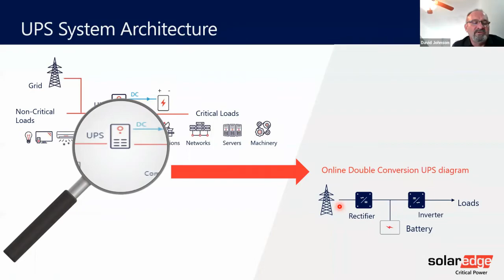So, limitations of a traditional monolithic system. We take a look at the two systems here. Traditional monolithic is one large component. And if you want redundancy in that, and you have all of these components in here, it also goes to, as we'll talk about, the maintaining and repairing of it. So if you want redundancy, and we're giving an example here of 240 kW, to have redundancy in this system, you have to add another complete 240 kW module. You have N plus 1 redundancy, and in this instance, you also have 2N.